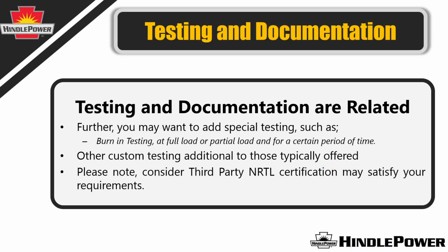Also notice that you may be getting NRTL certification, similar to UL or CSA. That's safety testing, so it's not part of the testing done during manufacture—it's part of the testing done in advance, during the design.